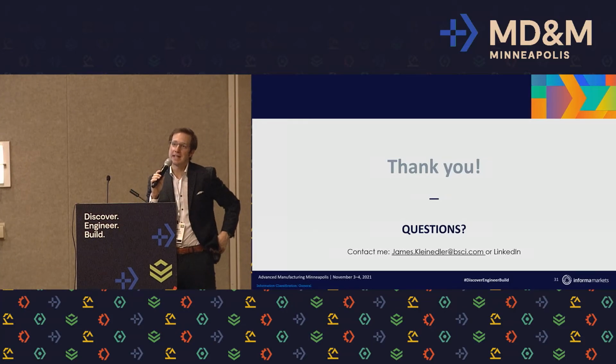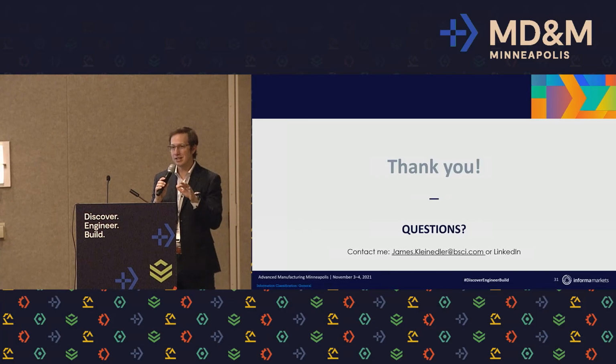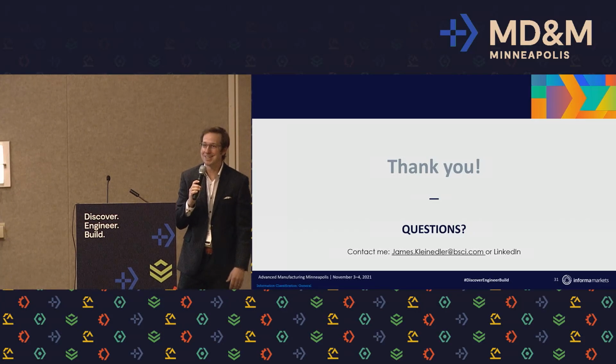Yeah, so the question is about how to landscape FDA guidance documents that might be relevant to your device, and it's a really good question. I'll just tell you what I do. I'll search not only on FDA's website, on their guidance document page, for keywords related to my device, but I'll go to the 510K summaries or the summary of safety and effectiveness data from PMAs that are most closely related to my device, which have very similar functionality or claims. Those summaries will oftentimes list what standards and which guidances were followed. Not all of them do, but if you take a sample of those, you should get a couple of hits on, directionally, what I need to be doing from a guidance document perspective. That's the best way that I've come across doing it. Yeah, that's what I do.